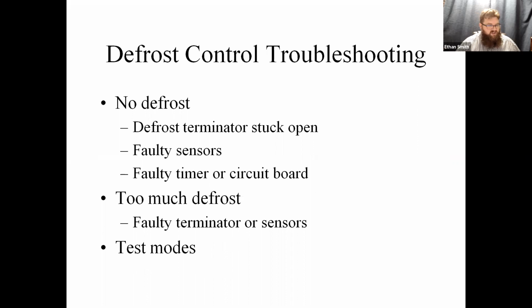The sensors are simply thermistors where you have to go in and check the temperature reading that those thermistors are giving you. On all the Trane and American Standard units, that's a 10K thermistor that they use universally. You get into other brands, they use 20Ks, or if you're into the ductless mini split systems, who knows? You're going to have to refer to each individual unit to find out, and each individual sensor actually, to figure out what those thermistor resistance values should be at certain temperatures.